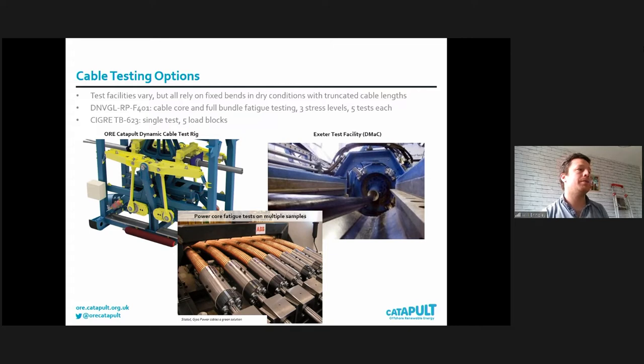The current standard for certainly large high voltage or medium voltage power cables is this CIGRE TB-623 standard. And typically for a fully completed cable, you only have to run one test and you run a range of curvatures to capture the response that you see in reality. The problem with this test is that you only really can confirm a failure when you cut into the cable destructively. So sometimes it'll tell you you have a failure, or hopefully when you've run to the end of the test and you cut in, there'll be no damage and you say there's no failure.